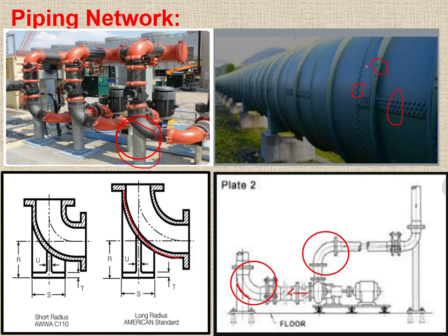okay. So the size of these rivets, the size of the elbows, the size of the nuts and bolts, and the size of the couplings must all be installed according to the standard pressure class. Okay, so this is very practical. We see what the pressure class is, and based on that we select the size of the rivet, the size of the nuts and bolts, the size of the flanges.